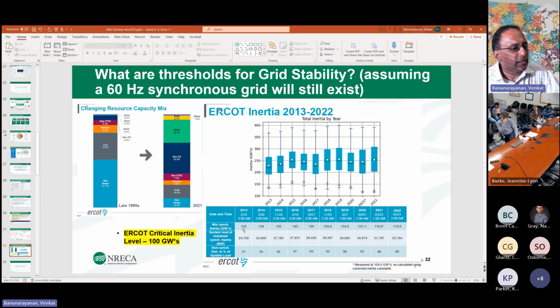So you can see that it went from 132 gigawatt-seconds down to 115 gigawatt-seconds. Not yet at 100, which is the threshold, but it's decreasing. The other thing is the percent of load being served at a reduced inertia is also increasing. So you have two effects happening: the inertial threshold is decreasing, and the percent of load served by a lower inertial threshold is also increasing.